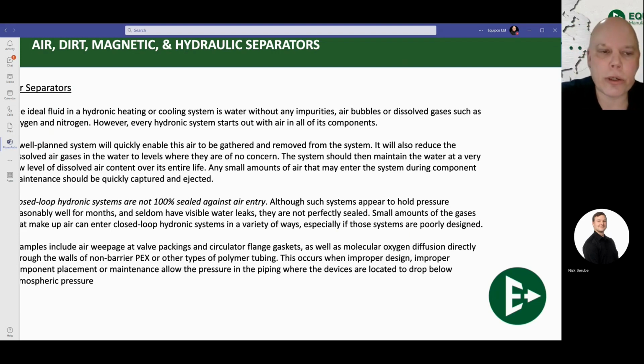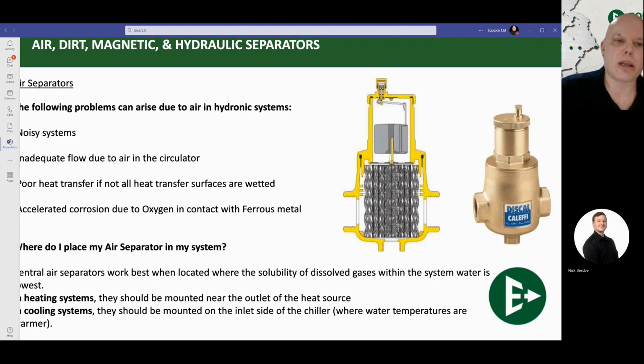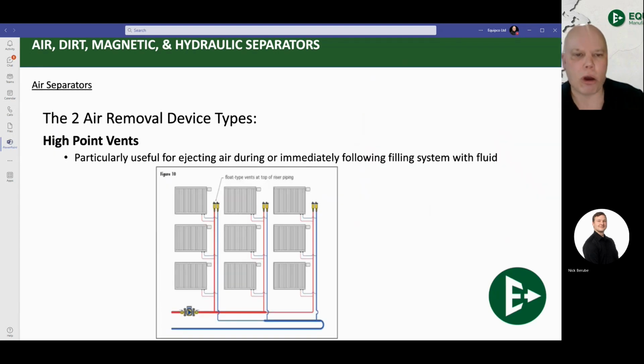Now, air separators should be installed at the hottest point of a system. If you've ever boiled a pot of water, air starts to come out of solution as the water temperature gets hotter. As you get the higher water temperature, air comes out easier. That's where you want the stuff to come out, so that's where you want these things to be inside of a system. They're going to be on every single system. Usually it's also where you tie in the expansion tank for the most part, but just know that you do need to put them in. It's always best to put them right after the boiler. It should be the very first thing that the boiler sees, where the water is going to be the hottest.